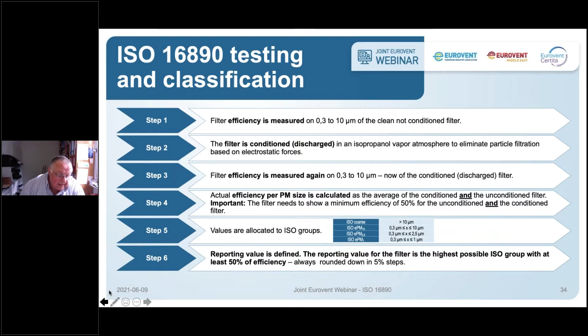After that, the reporting value is defined, and that's the value you find on the label. The reporting value for the filter is the highest possible ISO group with an efficiency of at least 50%, and that's always rounded down in 5% steps. That sounds a little bit difficult, but it's quite easy. You see that in the next slide.